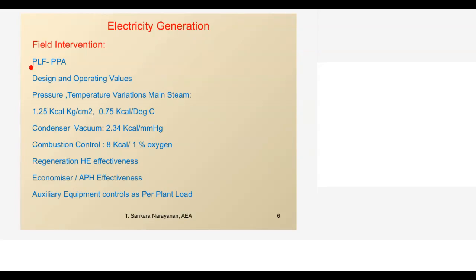See, today PLF is predominant in all the industry, the generating power plants, because in India today we are almost surplus in power. Very few sections of the country have power shortage. Otherwise, even for a very good power plant, their PLF is reduced because of the existing PPA. If the PPA itself is putting a restriction, I am forced to operate the plant at a lower PLF. The moment lower PLF is there, then we have to take care of all the other operating parameters. So a normal, good practice is that the design PG test value is compared with the operating value. Wherever deviations are there, at plant level we have to do certain intervention.